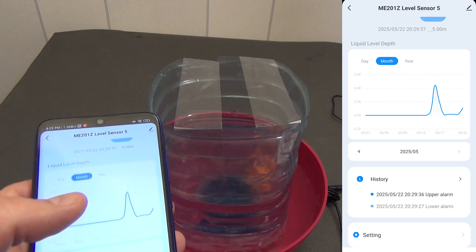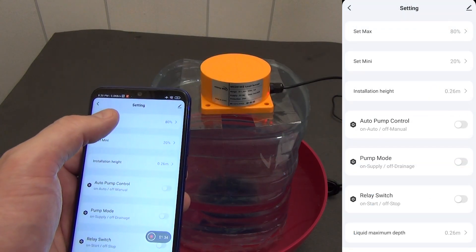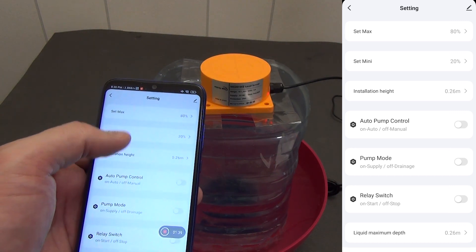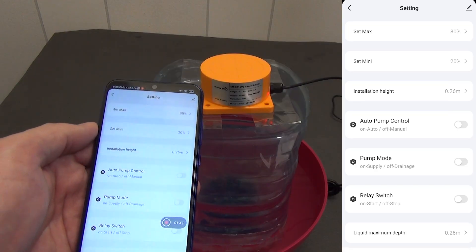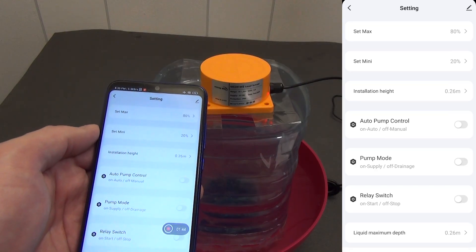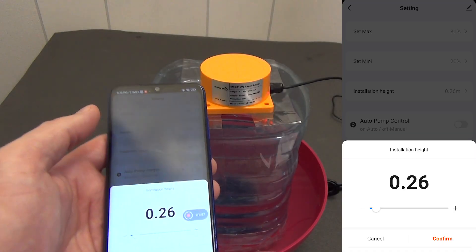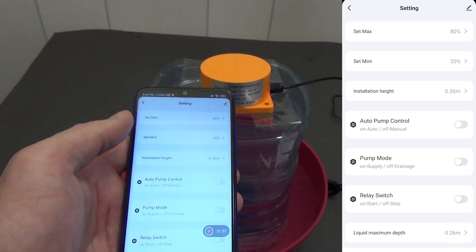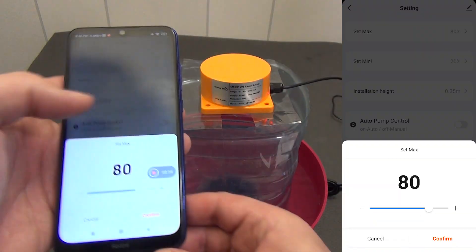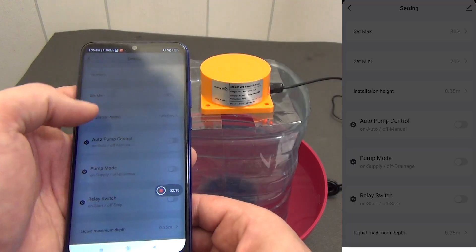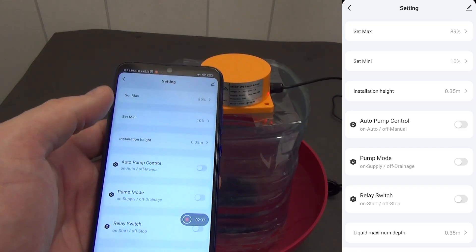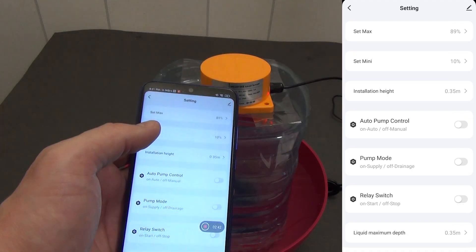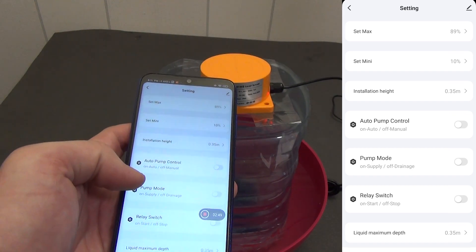Here we can set the following values: Set max, by default 80%. This is the level at which the alarm too high level will be triggered. The next parameter set mini, by default 20%. This is the alarm too low level. It is important to set the installation height parameter correctly. By default it is set to 5 meters. Let me change these parameters for the following tests. I will set the maximum level to 90%, the minimum I will set to 10%. And here is an important parameter, data on the height of your tank. Since the sensor cannot technically calculate how many liters it is, it needs the height parameter.